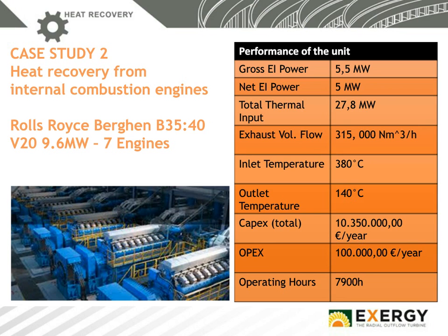In this case, the investment is in the range of 10 million euro. The operational costs are still very low, because compared to the internal combustion engines or the gas turbines, the operational cost of an ORC turbine is really, really low. Operating hours are higher, so we have taken almost 8,000 hours per year at full load. And the flue gas temperature is a bit lower than in other applications, because obviously the efficiency of the engines makes it 380 degrees at the entrance of the ORC. Also, the return temperature of the gas to the stack is in the range of 140 degrees, which is much lower than the 250 that we have seen before.